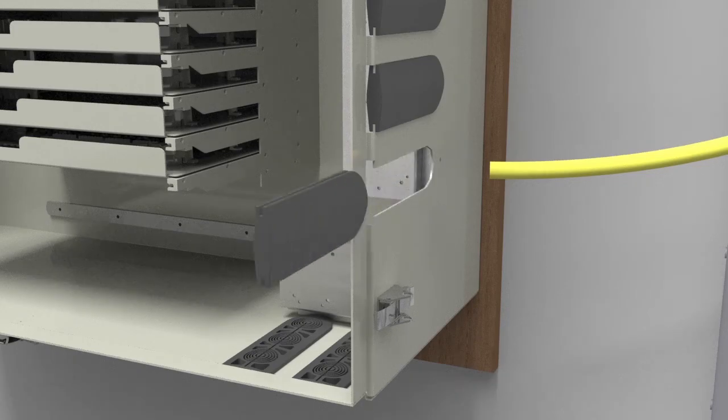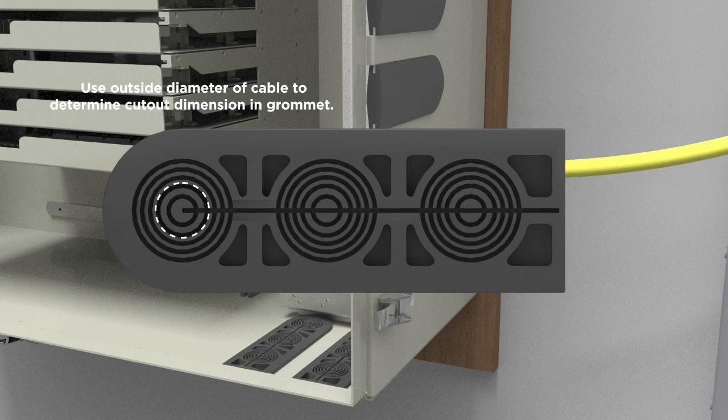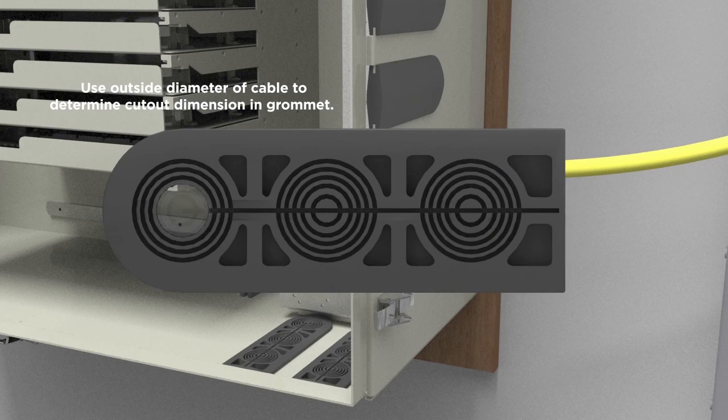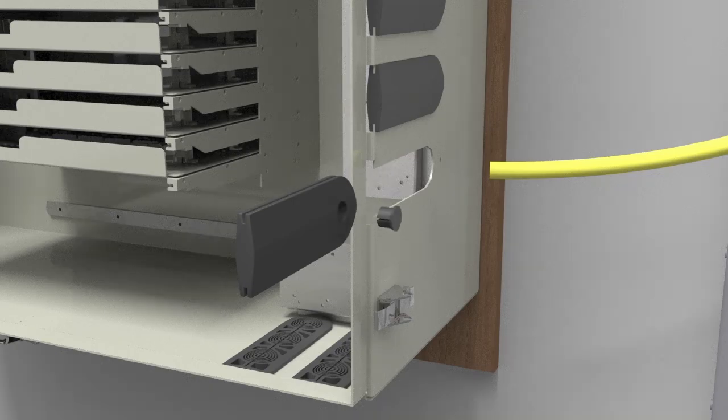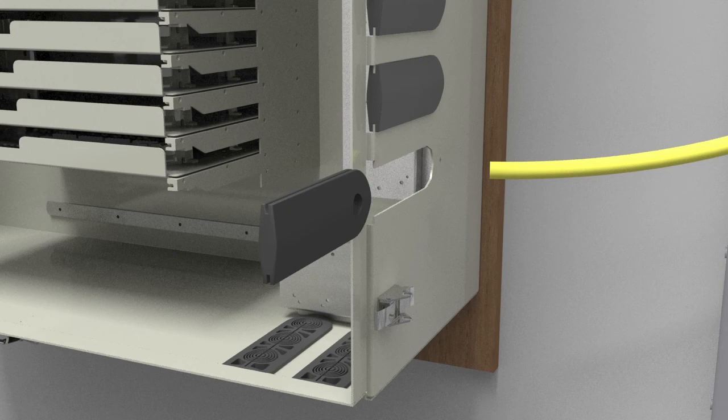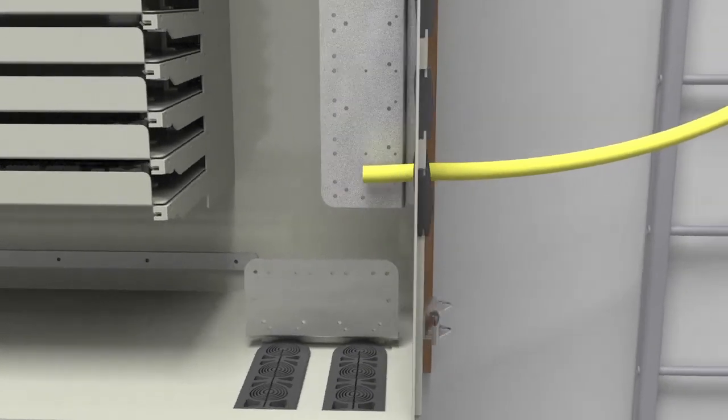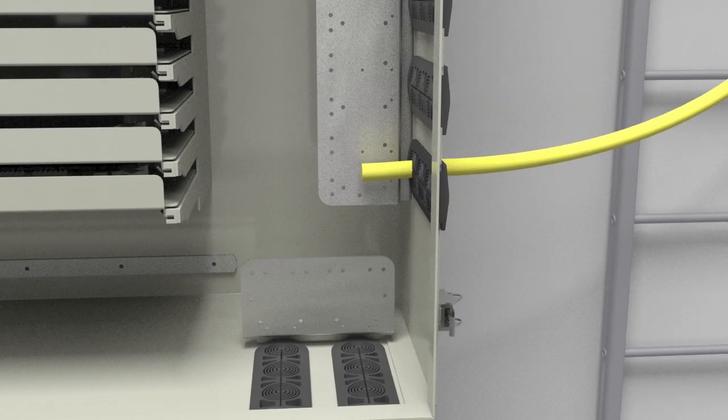Slide out the grommet. Use the proper tool to remove the cutout in the grommet that matches the outside diameter of the cable. Slide the grommet back into place and feed the IFC cable through the cutout and the grommet.